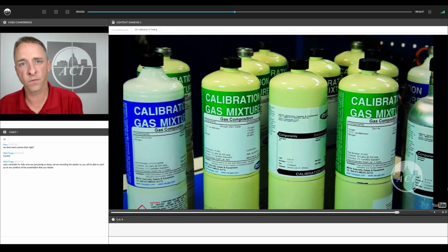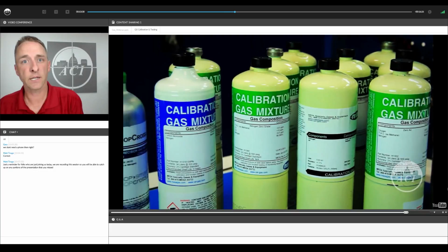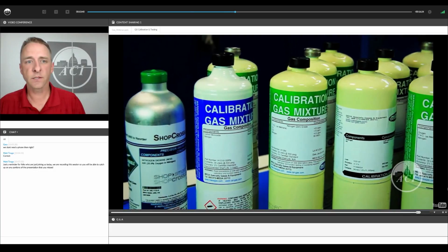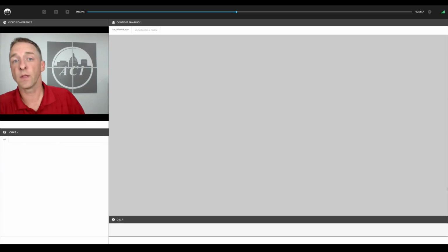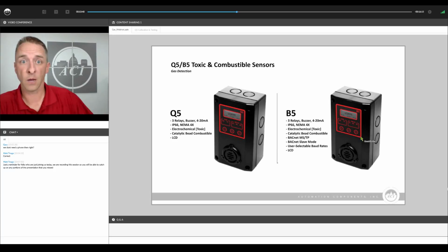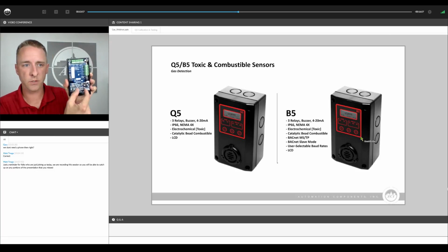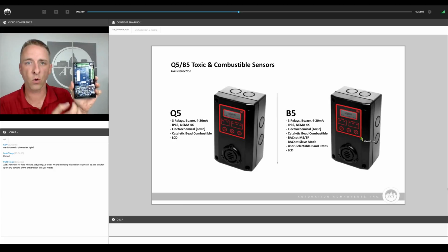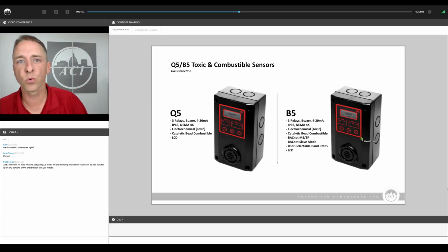These sensors do feature an ability to replace the sensing element down the road after they have worn out due to the electrochemical nature of the sensor. After they've worn out, you can easily replace the sensor. There are 2 screws here on the circuit board. You can just pop this board out and pop in a new board that's pre-calibrated. So it's very quick and easy to replace the sensing element on this unit down the road.